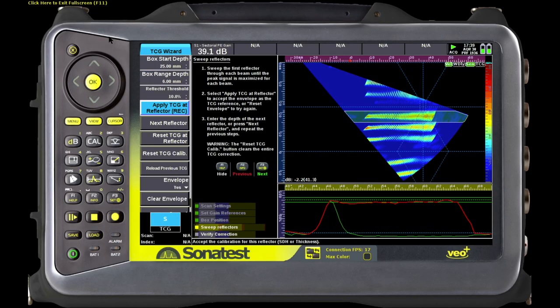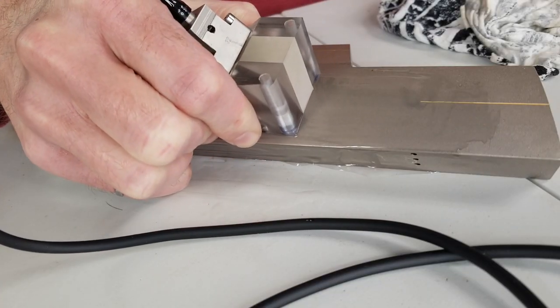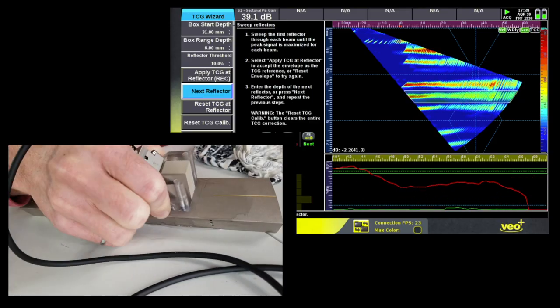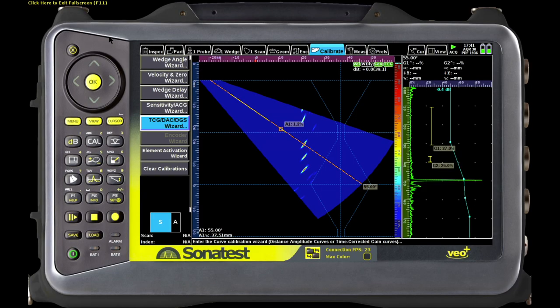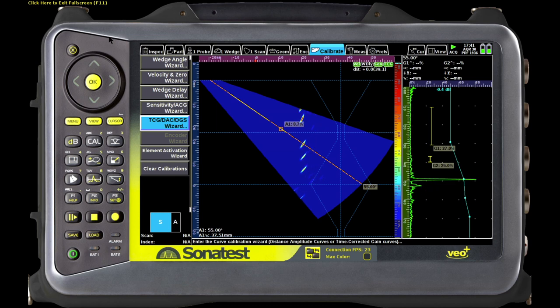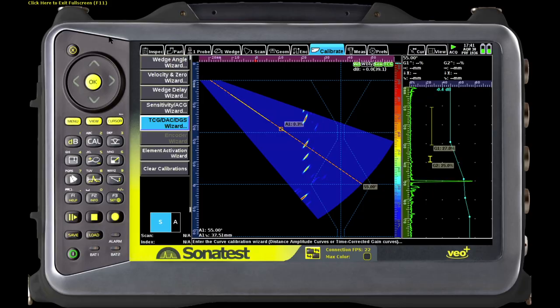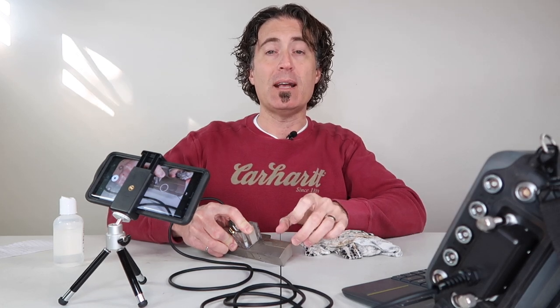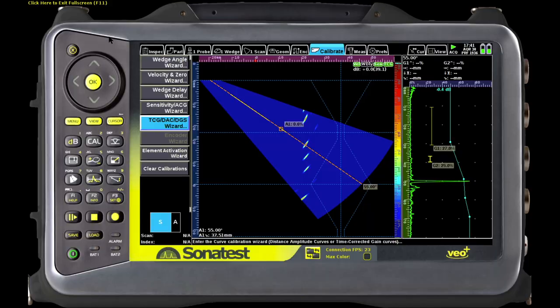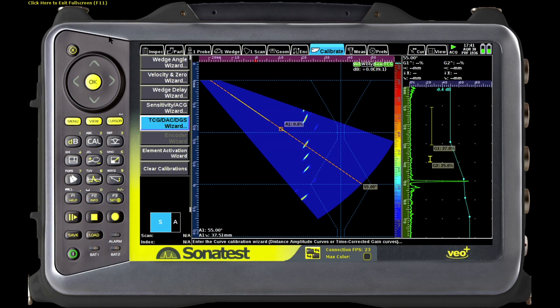We'll double check them when we're done and do all of the rest in fast forward. Now we're done our TCG. We can see that we've got our three hole signals lined up nicely on the first leg and into the second leg and even into the third leg. You can also see that there is no termination echo from the end of this block even though the holes are only about an inch and a half from the end — that's because the end of the block is tapered and we don't have the high angles and low angles talking to each other.